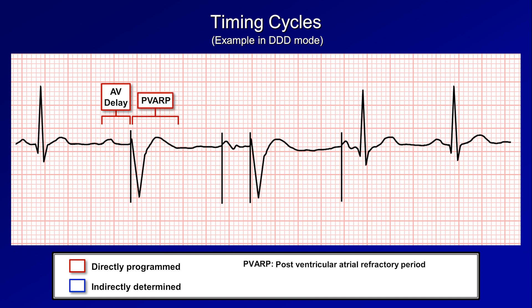Starting with this intrinsic natural P wave that is sensed by the pacemaker. The pacemaker then waits for the length of the programmed AV delay to see if intrinsic AV conduction occurs. In this case intrinsic conduction did not occur, so a ventricular pacing spike is delivered. After the pacing spike, the PVARP begins, extending some time into the T wave. Together, the AV delay and PVARP are known as the total atrial refractory period.